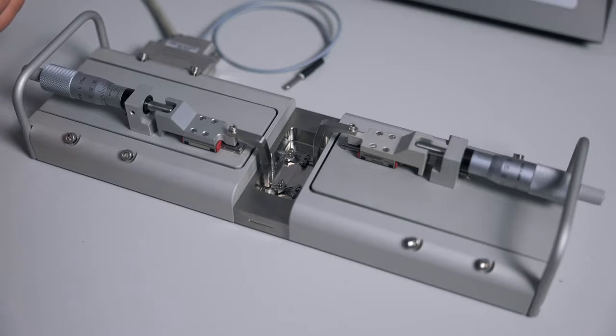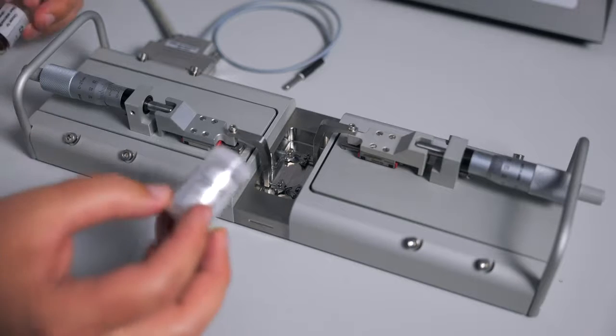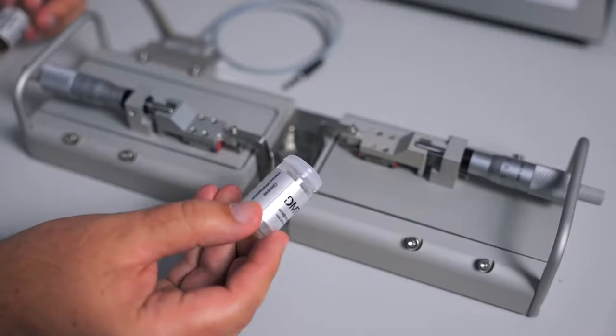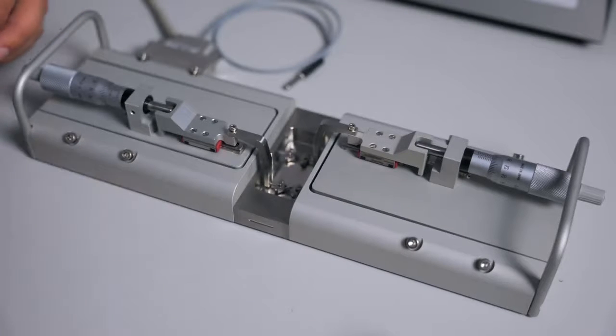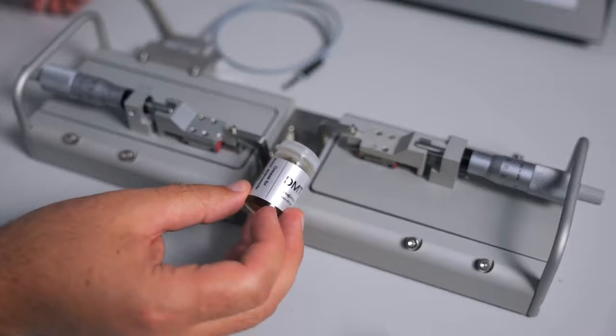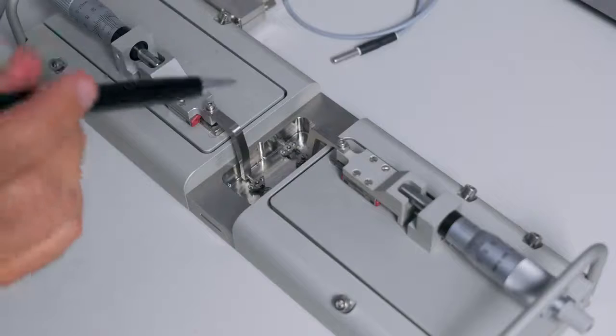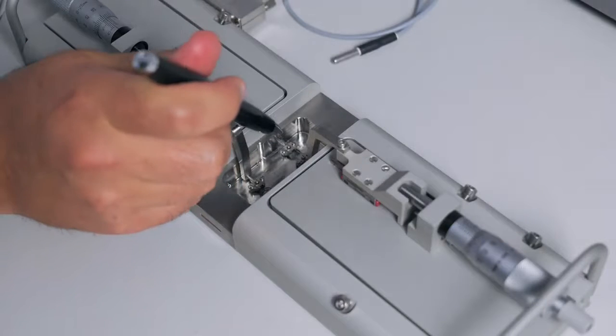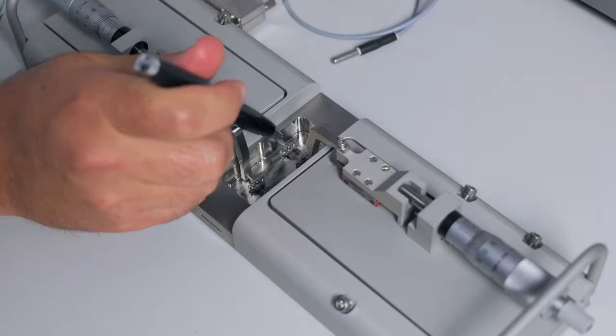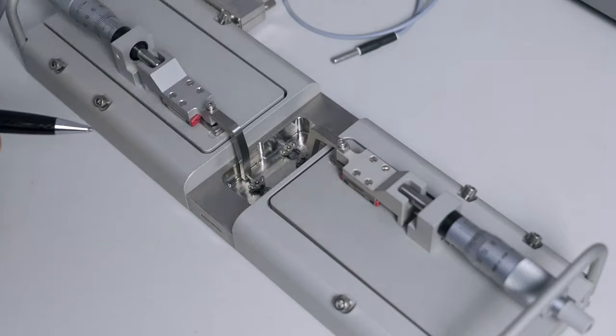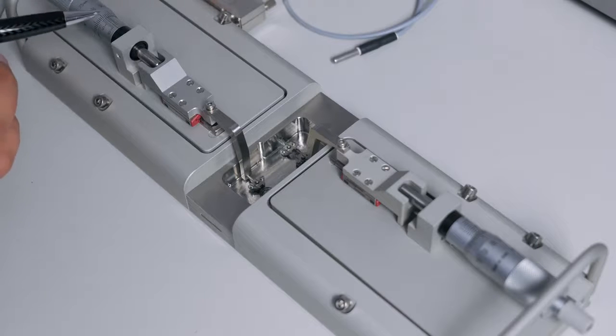For the more long-term maintenance procedures, you will need the clear grease that came with the myograph system, as well as the brown petroleum-based grease as well. After every cleaning, you should double check and make sure that the grease that is surrounding the arm coming out of the force transducer is thick enough to protect against any liquid getting into the force transducer housing.